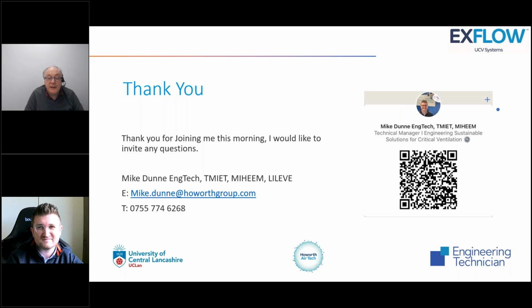Nigel Baker has asked, how independent can you be when validating your own canopy? It's a difficult one. On one particular site we've got, they have a clause that their approved supplier has to carry out all the validations. The way we split and differentiate between the two at Howorth is we have the capitals team and the service and after sales team. I look after the service and after sales team, so I draw a line down the middle and say that side of the system is delivered by the capitals team, and we work on behalf of the estates and facilities team, not the capitals team. I make sure it's fit for purpose and put together correctly, and we assess the commissioning document and everything you'd expect a validator to do.